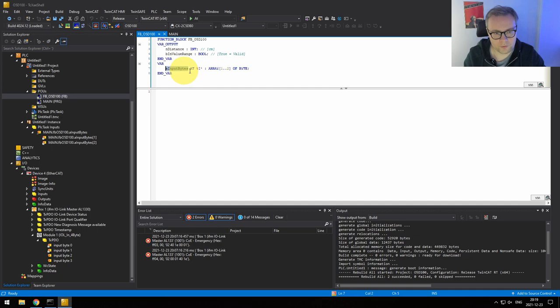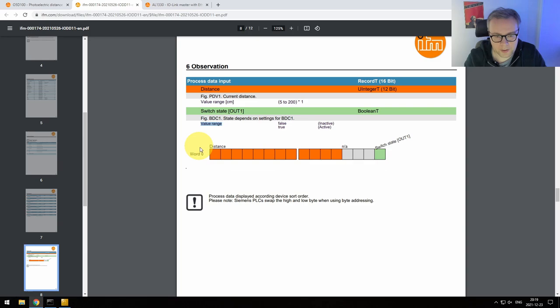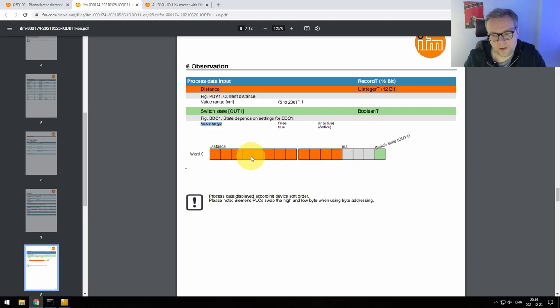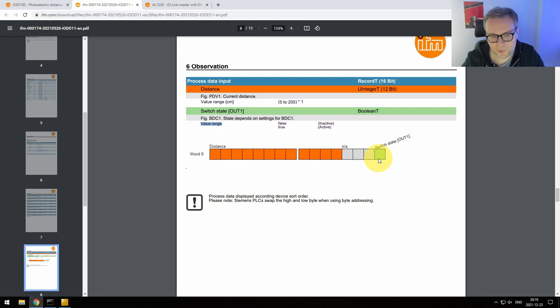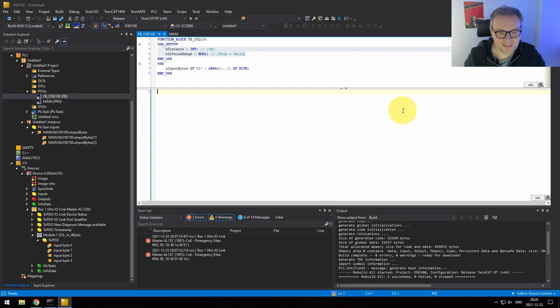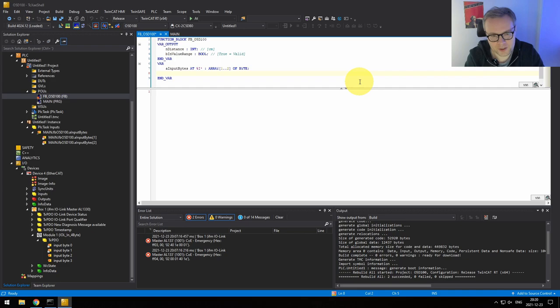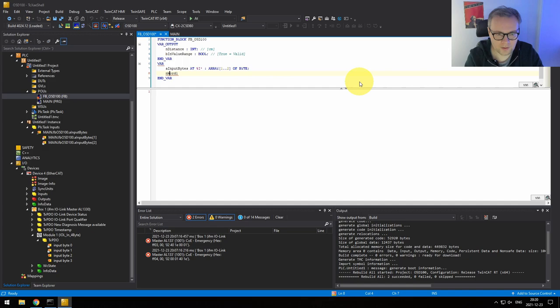Going back to the documentation, we have 2 bytes making one word — 16 bits total — but we're only interested in 12 of them. I want to convert both bytes into a word and then do some bit shifting to extract what we're interested in. I'll declare Word1 and Word2, and convert the first byte to Word1 and the second byte to Word2 using an explicit WORD conversion. When working with byte conversions, I always like to draw on paper or add comments to maintain a mental map of what's happening with the bits.